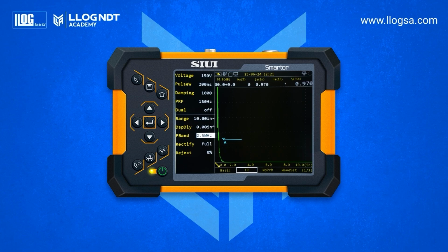Filter. Select a bandwidth that covers the center frequency of the transducer. In this case, for a 2.25 MHz transducer, select a range from 1 to 4 MHz. Rectification, full wave. Reject, 0%. In the Workpiece transducer submenu, thickness, 4 inches.